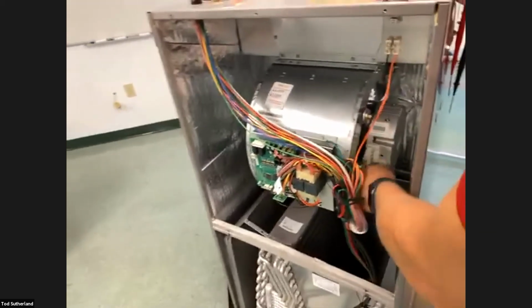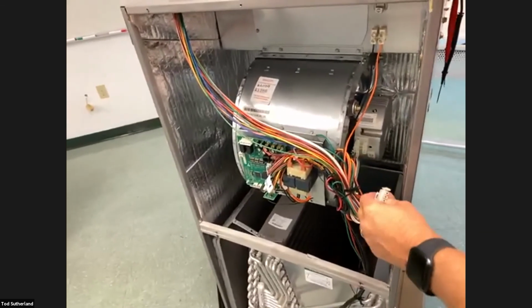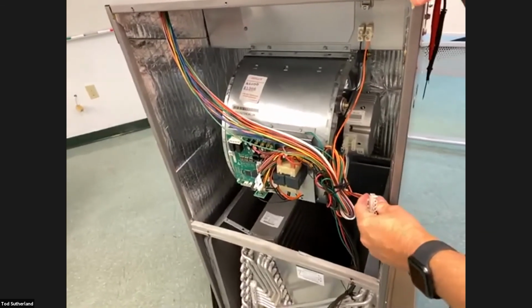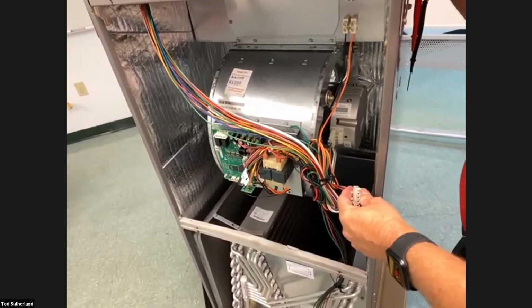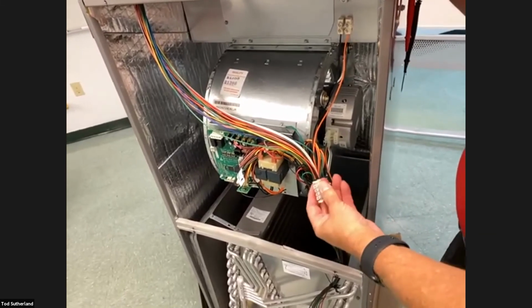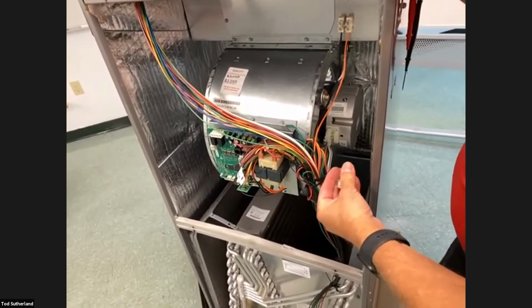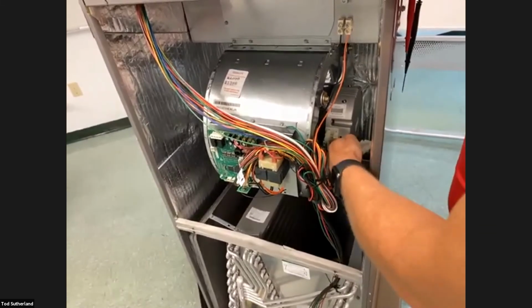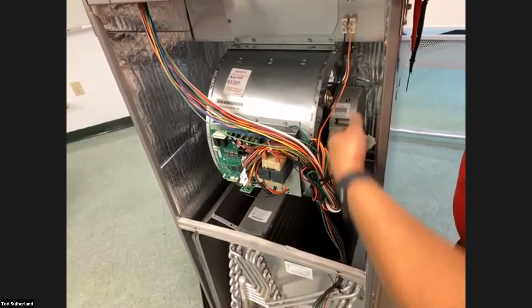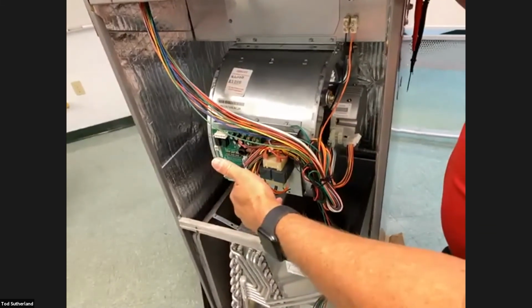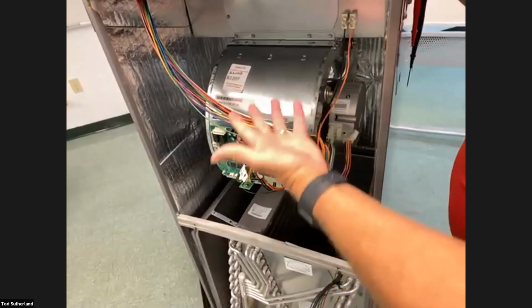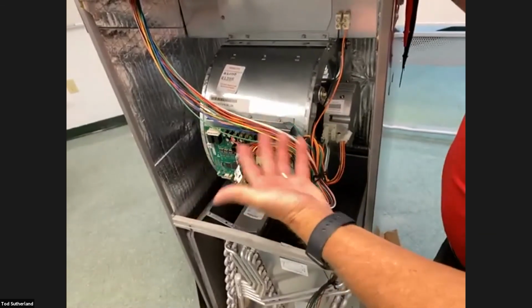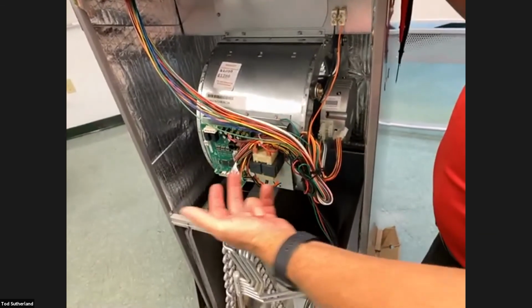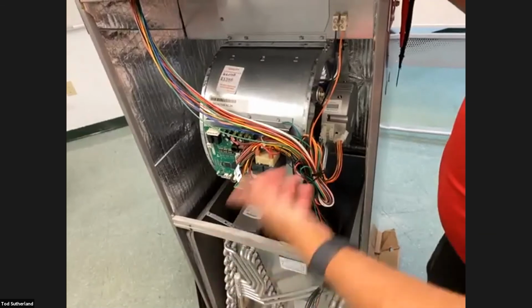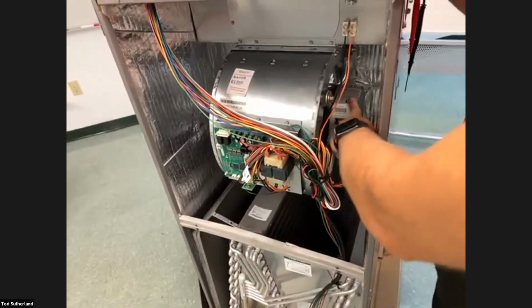Okay, so really the only way that you're going to be able to test this blower motor is if you have something like a Zebra tool or the TechMate tester, and you simply plug the TechMate tester into here, plug it into the motor. You attach it to your low voltage and click the button and your fan motor should come on. Okay, now some of the more advanced Zebra tools will give you more information than that, but that's really what you're going to do to check the fan motor.